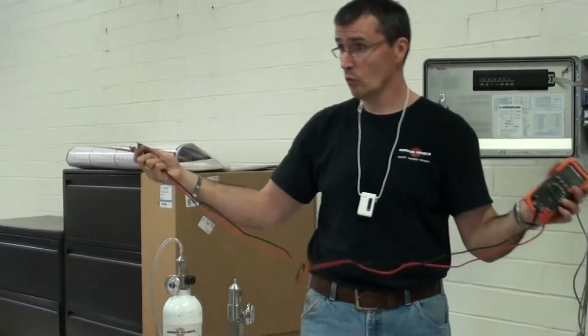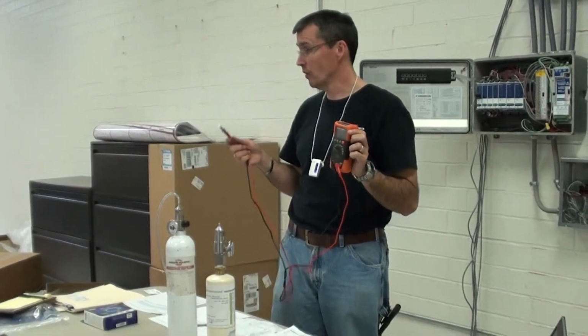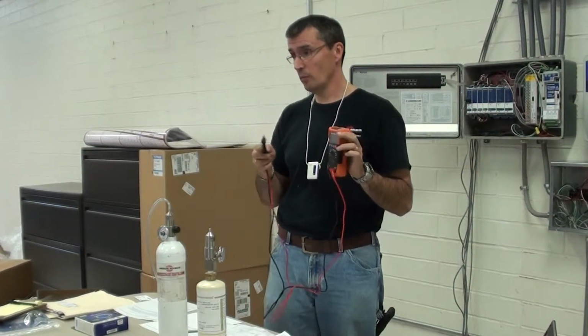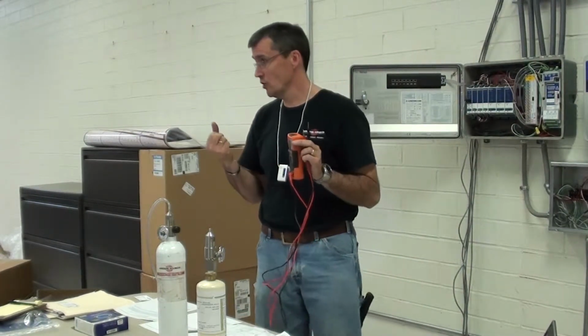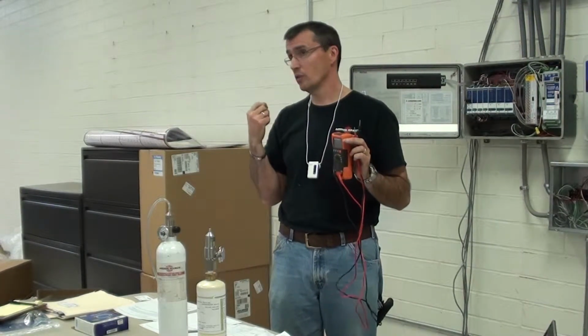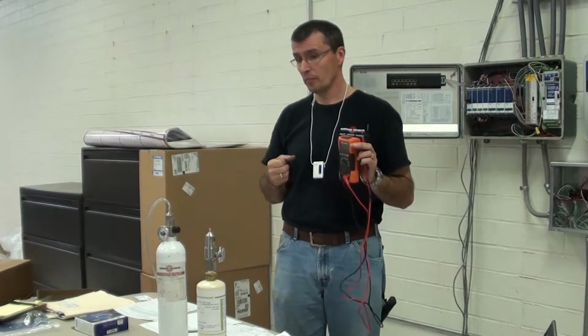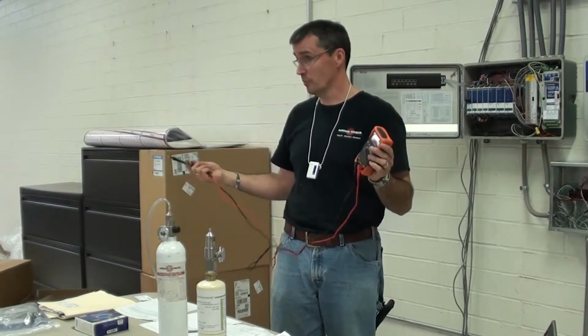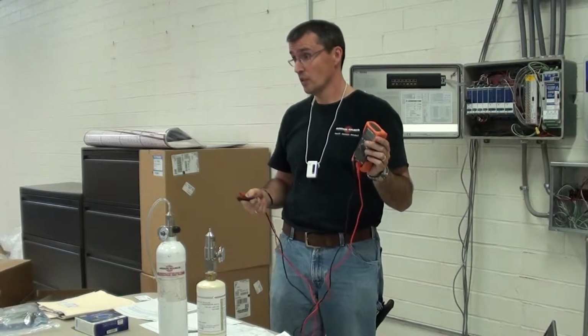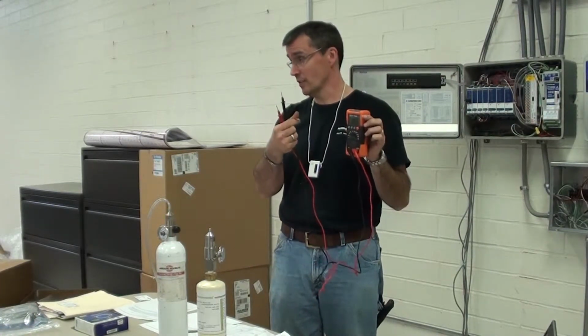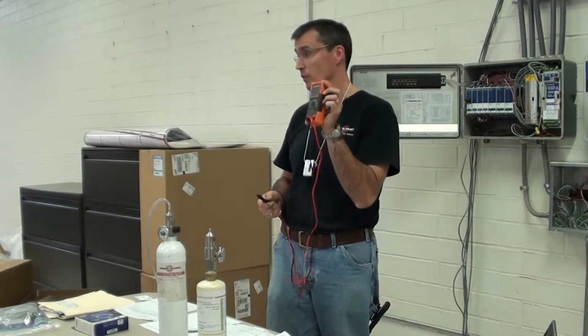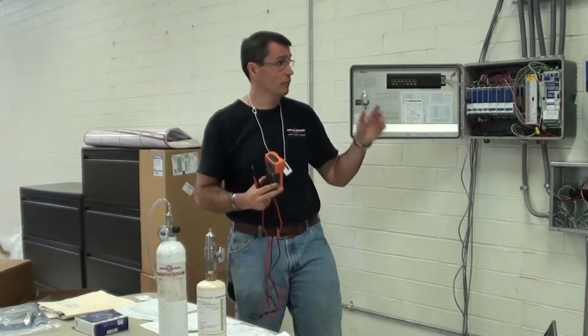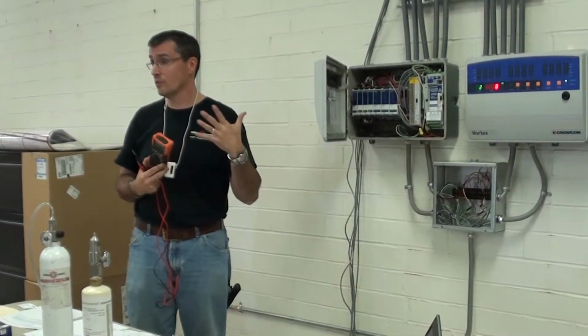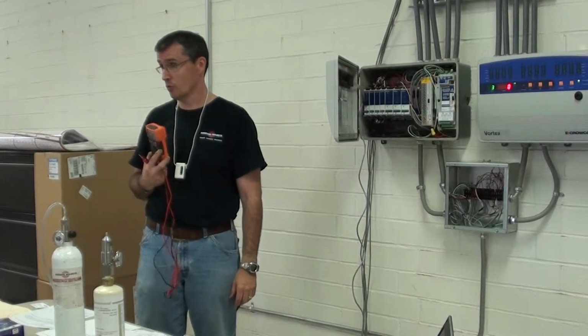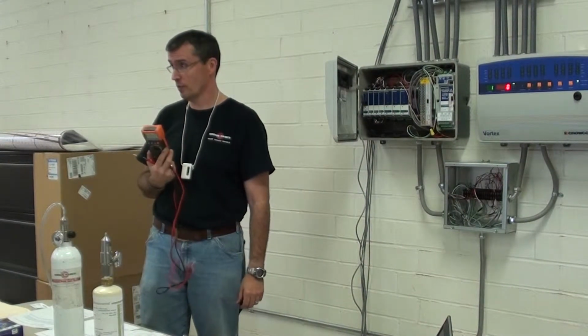Okay? So when you apply zero gas, and you have your voltmeter connected to TP1 and TP2, you're going to look for an output of 40 millivolts. If you're not reading 40 millivolts, you will see on your Xgard 2 potentiometers, one labeled zero and one labeled, is it calibrate or span? Cal, thank you. Cal. So when you're applying your zero gas, which pot are you going to use? Zero pot, right? So you're going to get in that potentiometer and turn it clockwise to increase it, counterclockwise to decrease it, and you're going to set it at 40 millivolts. When you set it at 40 millivolts, you want to verify on your control system, your Vortex, that it's reading 0% LEL. Okay? So 40 millivolts represents 0% LEL.